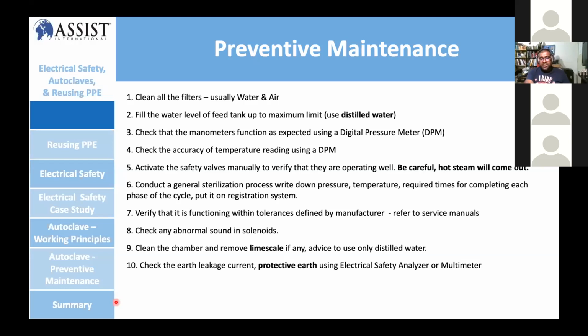Then conduct a general sterilization process. Write down the pressure, temperature and required time. See whether the phase cycle is working properly, and write it down in your report. Verify the function and the tolerance defined by the manufacturer. Refer to the service manual, and sometimes the user manual, because every brand and model has its own settings. Also check for abnormal sound from the solenoids, because it uses quite a lot of solenoid valves. You need to hear whether the sound changes properly according to the time.